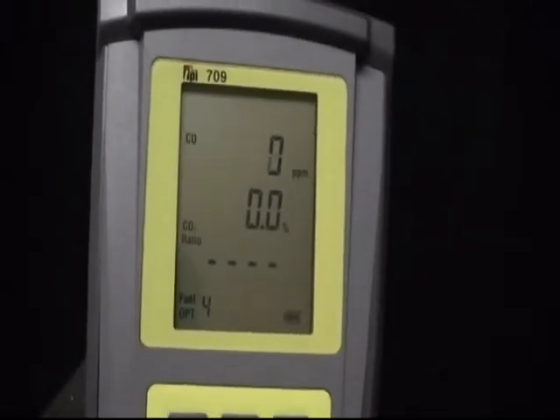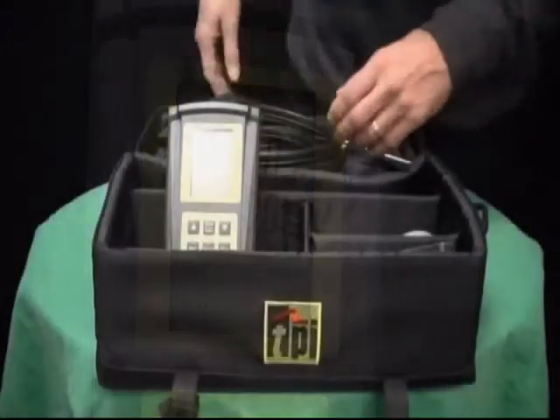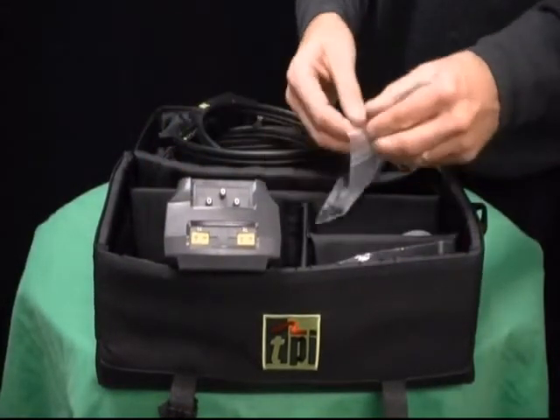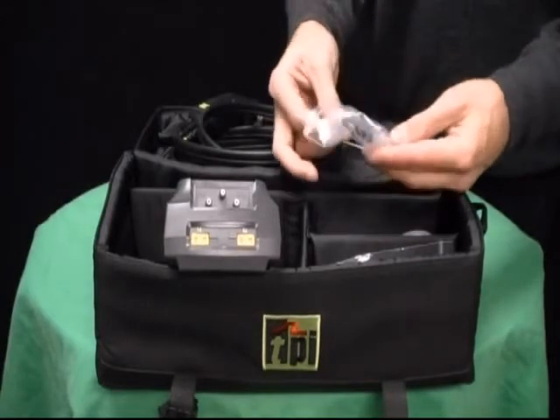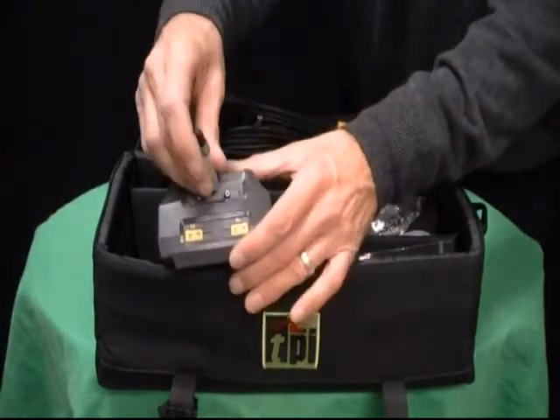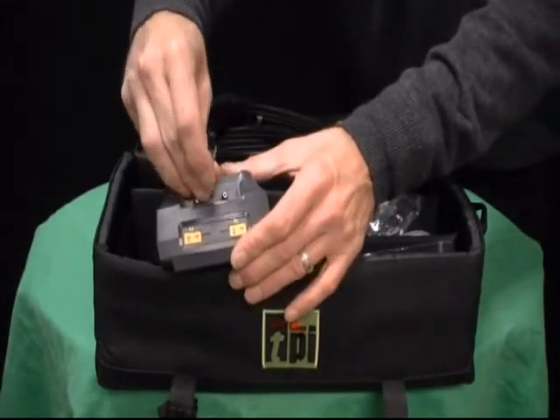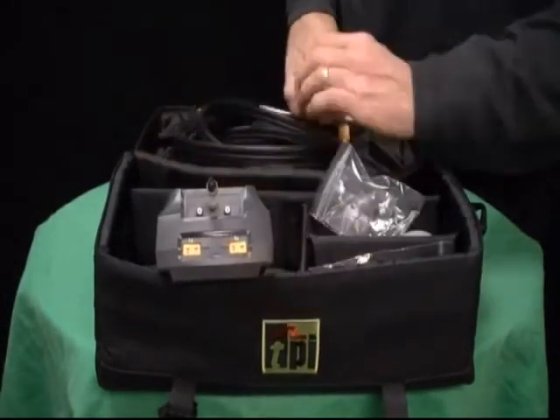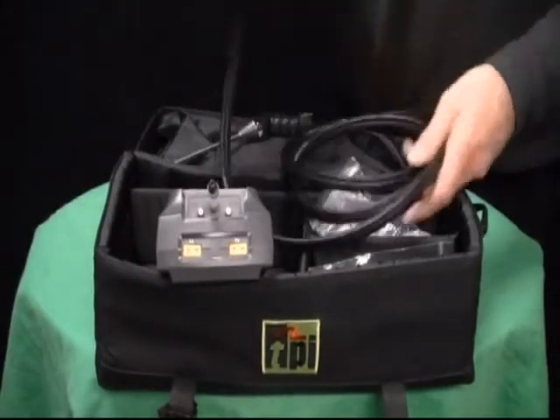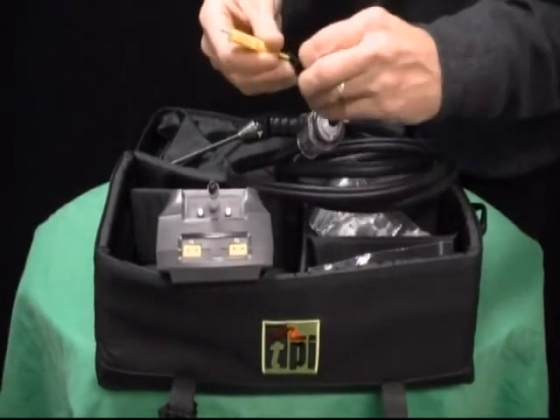The TPI 709 needs to be calibrated on an annual basis, just like the other combustion analyzers out there on the market. The sensors are electrochemical, meaning that they will deteriorate over time, and that is regardless of how much they are used. So every 12 months, it's important to send the analyzer in and have it fully calibrated and looked over by our staff here at TPI.